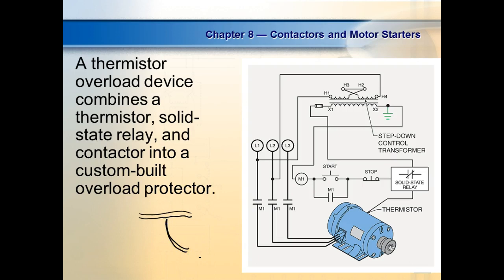So what we do is we send the load current through the strip. It's got a little bit of resistance. It creates heat. If it gets too hot, what does it do? It bends up and opens the circuit up. Well, what happens when it cools down? It goes back down. This is what's used in your circuit breakers, but your circuit breakers have a spring in there that doesn't allow it to automatically reset, right? You understand? In fact, if you have a circuit breaker that trips, what do you have to do? You have to turn it all the way off, turn it back on to reset that latching mechanism. So it actually latches. If it didn't have that, it would reset itself.